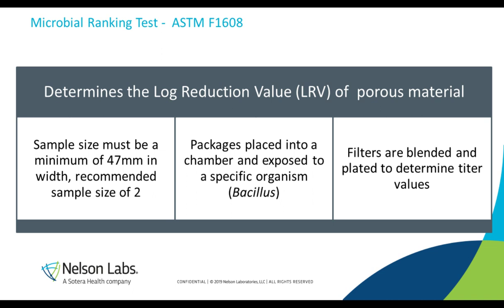The standard does have a recommended sample size of 2, and the way that it works is we take these swatches of material and we expose them to an organism, and this organism is actually the very same organism that is used in the ethylene oxide sterilization validations, Bacillus atrophaeus, so it's a spore former. Upon being exposed to these organisms, we then remove the samples, and the filters that are laid beneath the material are blended and counted, and we determine the amount of organisms that passed through the material. This value then calculates out to what's called a log reduction value. The log reduction values can vary anywhere from 0 to 6.1 or 6.2. The higher the log reduction value, the better retention of the materials.